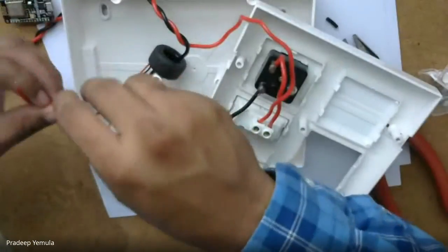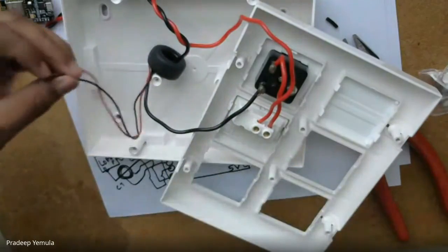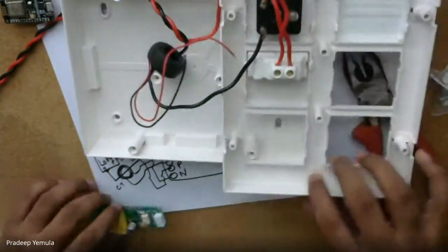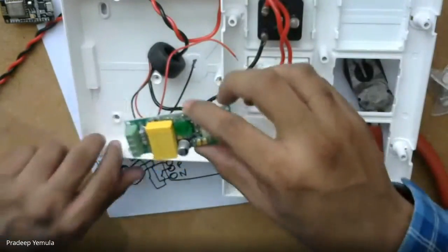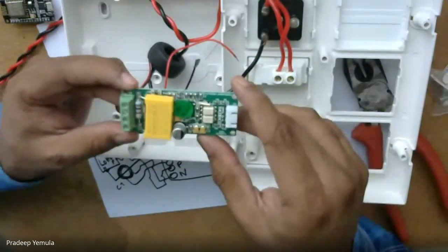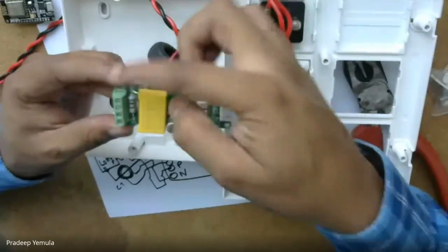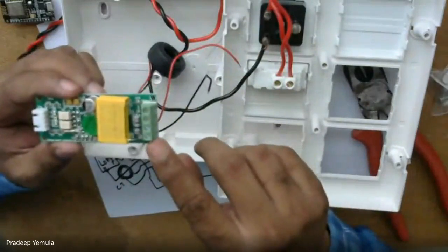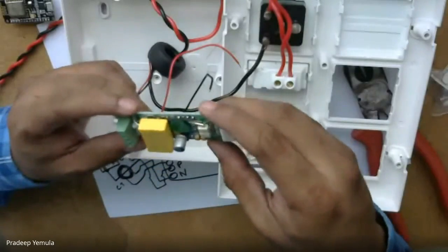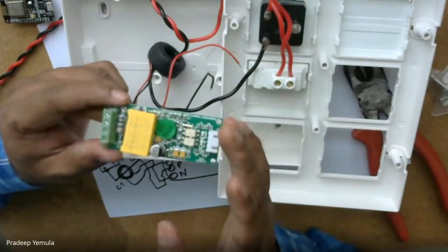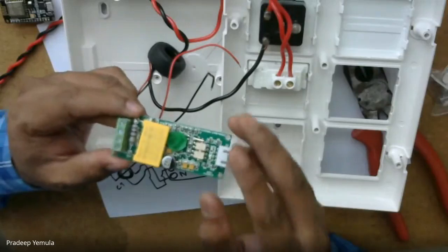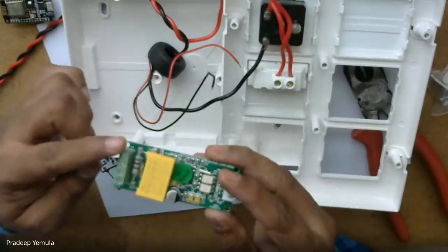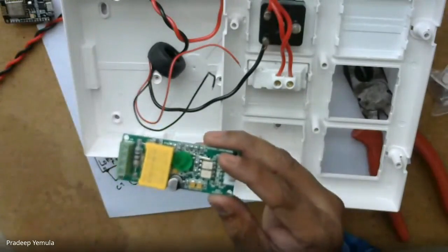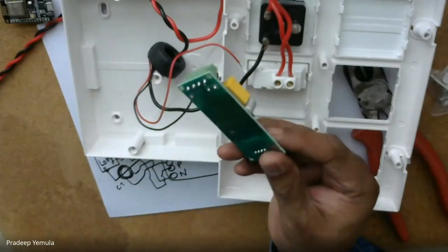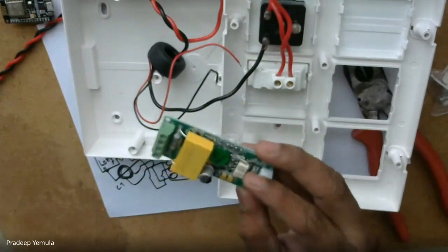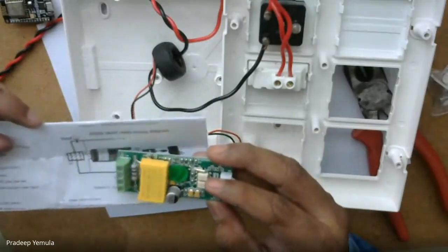Now this, as I already mentioned, we connect to S1 and S2 in our component. If you see in this, again you need to be careful with the orientation. The top one is S1, but if I turn it like this, now the bottom one is S1. So be careful how you are connecting. If you keep the electronic side on the right and the power side on the left, then the top one is S1, and then S2. How do I know? Either you follow the markings on this particular device, or you look at this particular sheet.